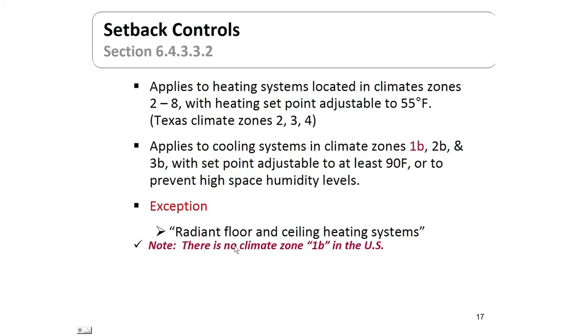Setback controls allow you to set back the temperature at night when you don't need as much heating or cooling. This applies to heating systems in climate zones two through eight, and those set points have to be adjustable to 55 degrees Fahrenheit or less. On the cooling side, this applies to climate zones 1B, 2B, and 3B, where the set point has to be at least 90 degrees — including to prevent high space humidity levels. The exception is radiant floor and ceiling systems. Note that there is no climate zone 1B in the United States.